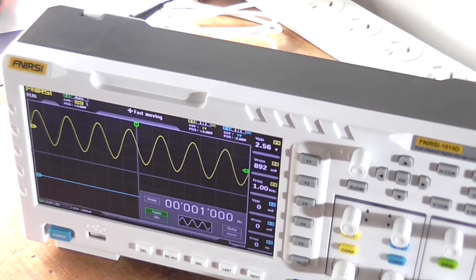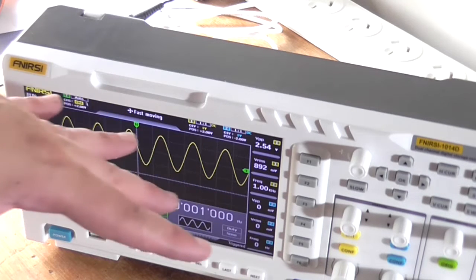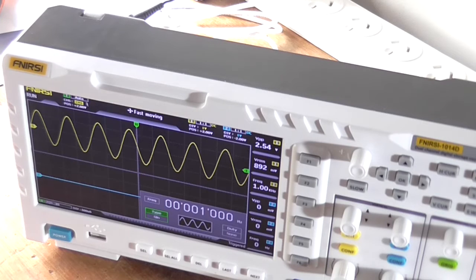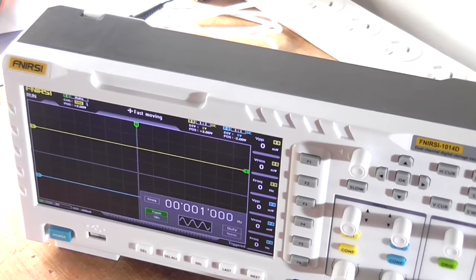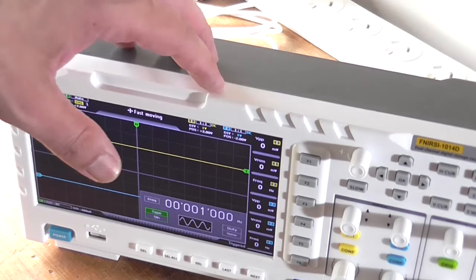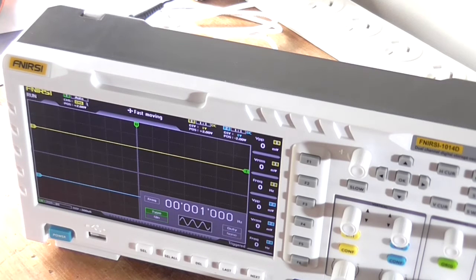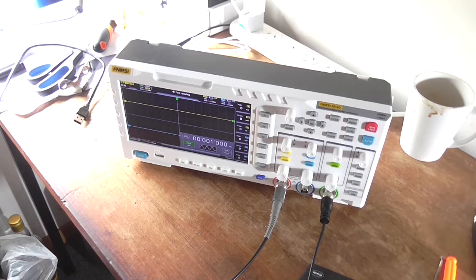Also, the other good thing about this is, because of the way it's powered, this oscilloscope is actually isolated from the mains earth. That means the ground lead on the end of the probe is also isolated from the earth. And I lost the signal because the lead came off. So that means you are not going to damage your oscilloscope when testing high voltage equipment that is earthed, by earthing the oscilloscope in the wrong point of the circuit, if you know what I mean. So you're not going to blow the equipment up, and you're not going to blow the oscilloscope up, especially for valve equipment, but for that you're going to want at least a times 100 probe. Times 10 gives you a maximum of 400 volt DC, so times 100 would give you 4000.